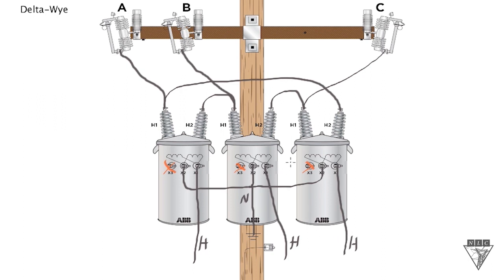So one of the benefits of a delta Y connection is on the primary side, you can hook it up to a three wire system like a delta or an ungrounded Y system, or you can use a four wire system like a grounded Y system which has a neutral. On the secondary side being a Y connection, the load is balanced equally between all three transformers, so that's a nice benefit.